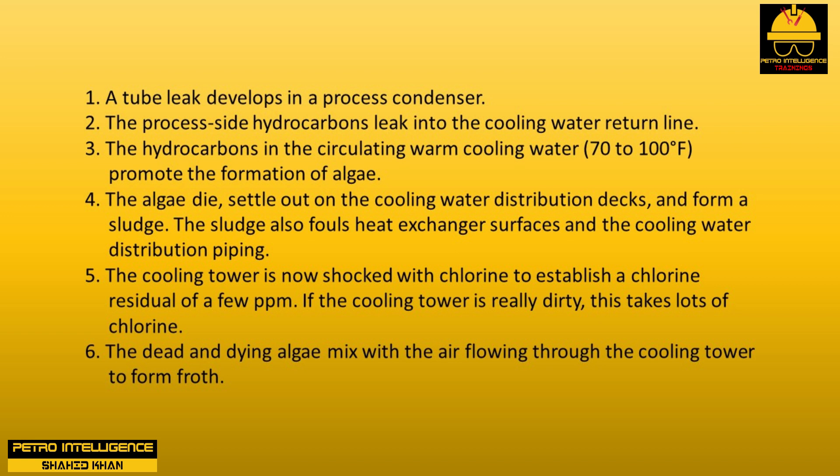Four, the algae die, settle out on the cooling water distribution decks, and form a sludge. The sludge also fouls heat exchanger surfaces and the cooling water distribution piping. Five, the cooling tower is now shocked with chlorine to establish a chlorine residual of a few ppm. If the cooling tower is really dirty, this takes lots of chlorine. Six, the dead and dying algae mix with the air flowing through the cooling tower to form froth.